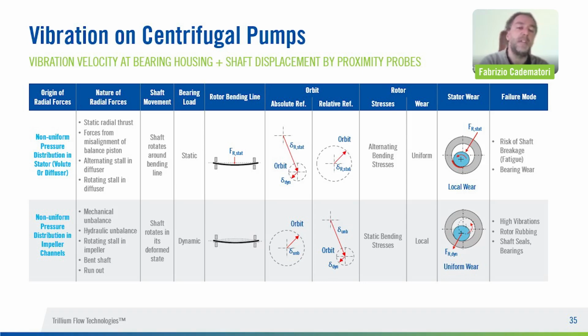In the absolute system, the orbit is reduced to a radial displacement, while in a relative reference frame, the orbit is almost circular. In contrast, with a non-uniform pressure distribution in the rotor, the shaft rotates in its deformed state, with a static bending stress in the shaft. In the absolute system, the orbit is pretty circular, and in the relative reference frame, the orbit is reduced to a radial displacement. Okay, next slide, please.